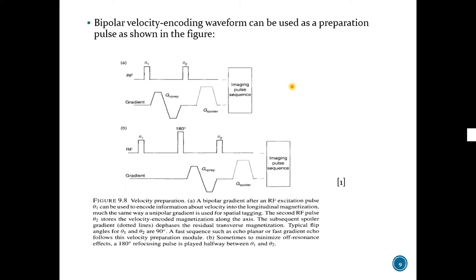Where do we apply bipolar velocity encoding gradients? They can be applied after RF excitation, before the imaging pulse sequence, as a preparation. Spoiler gradients dephase transverse magnetization, and actual imaging pulse sequence may follow. Of course, it is not the only way to do that.